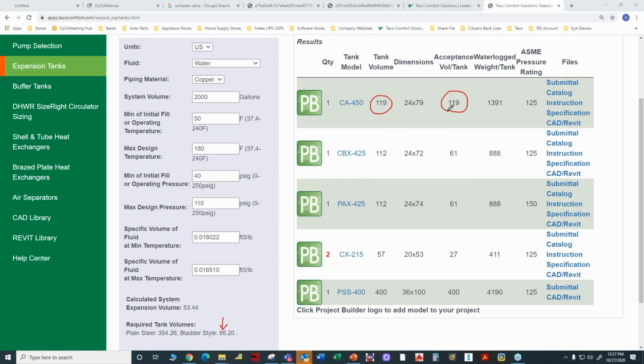Is 119 gallons for the bladder. Now, since the bladder volume is equal to the tank volume, then we say that this is a full acceptance tank. If you recall from my previous discussion, I said that whenever the bladder volume is equal to the tank volume, it's called a full acceptance. So the first selection the software has made meets the requirements, and the acceptance volume has to be greater than the expansion volume. In this case, that's approximately 53 gallons. So that first tank meets the criteria.